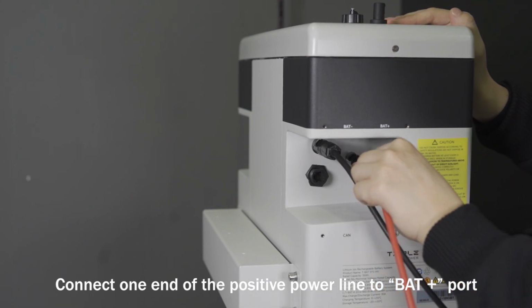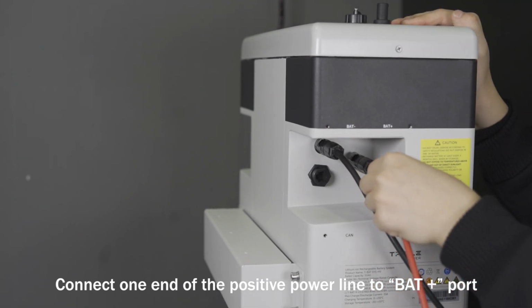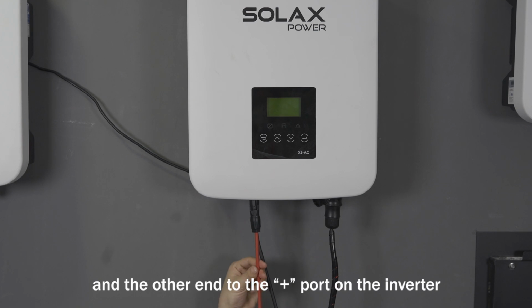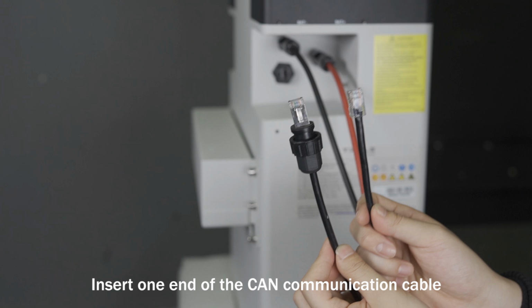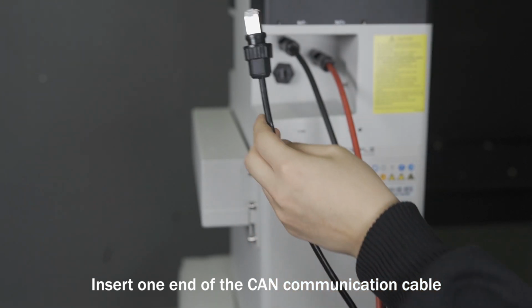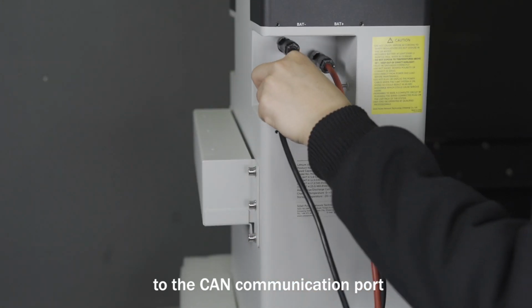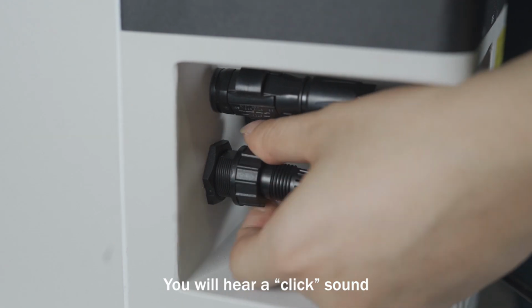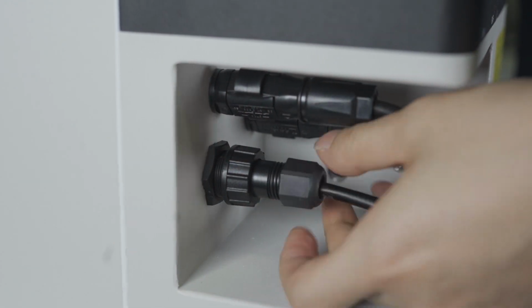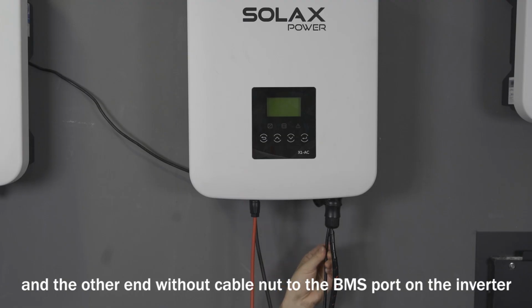Connect one end of the positive power line to BAT positive port and the other end to the positive port on the inverter. Insert one end of the CAN communication cable to the CAN communication port. You will hear a click sound. And the other end without cable nut to the BMS port on the inverter.